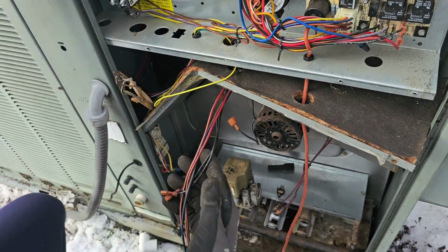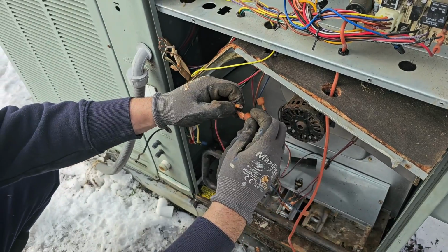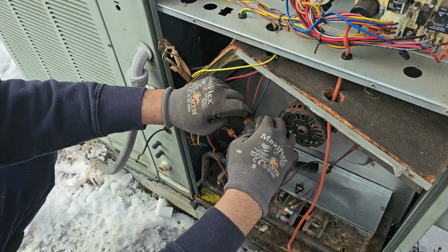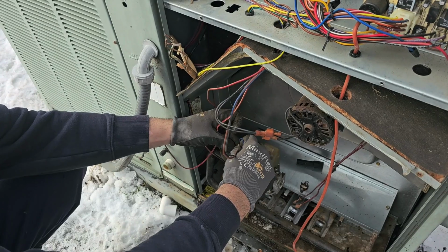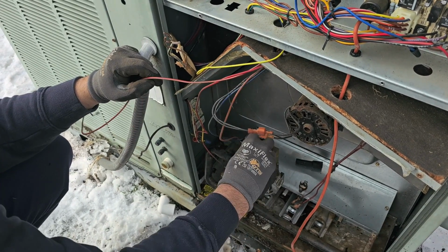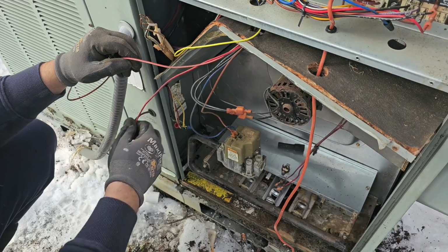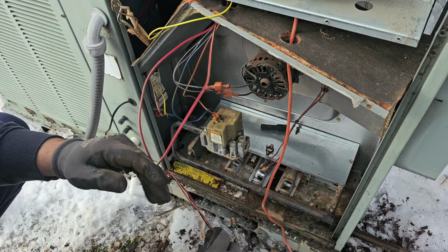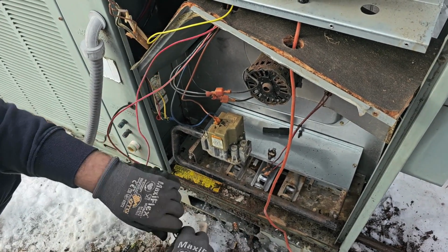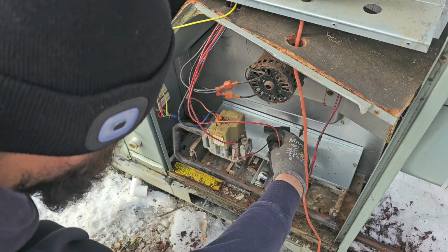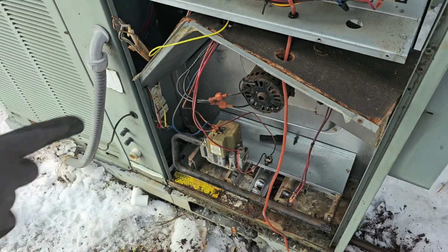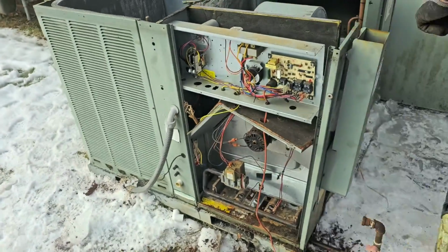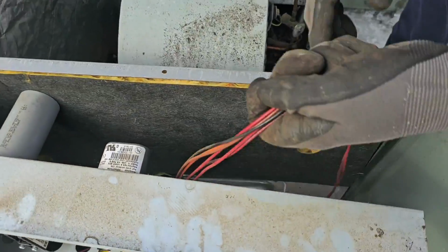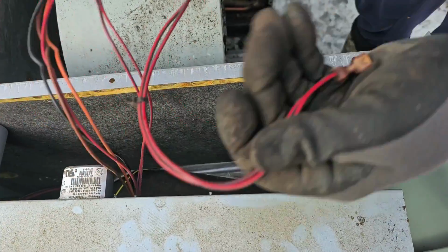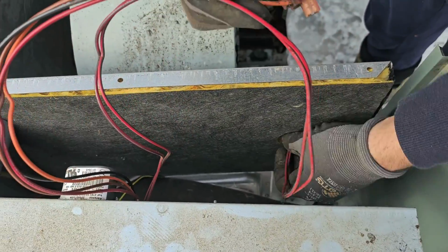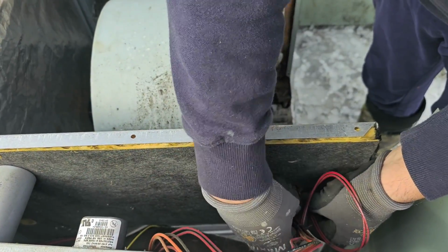So see there? Now we got all our wires ready to be connected. Inducer motor, gas valve, see? And then we got a couple wires to our rollout switch. Our other wires, before we put the top back on, they come through here. And you've got 2 for your limit switch, high limit switch, and you've got 4 for your blower motor.